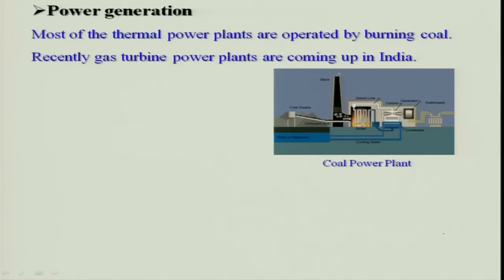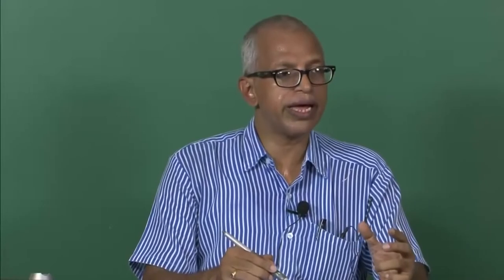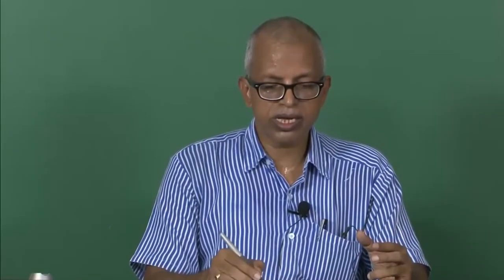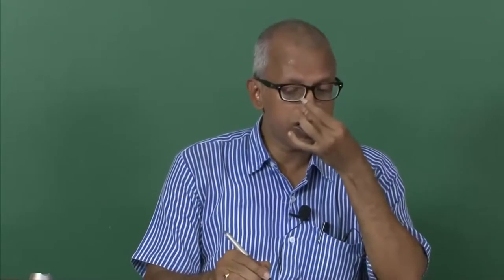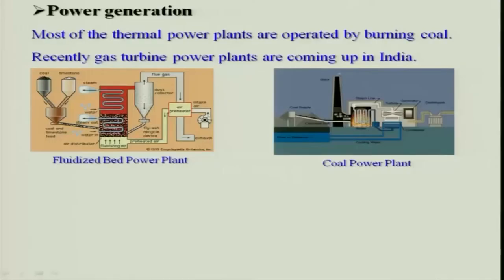There are several technologies for coal power plants. Traditional boilers are there with various kinds. There is powdered coal combustion, fixed bed grate combustion with steam turbines. Recently, fluidized bed combustors are being used — air is used to fluidize the particulates so they are suspended in air for better combustion. There are also circulating fluidized bed combustors, which circulate the particulates so they do not go into the atmosphere to the same extent as in traditional power plants.